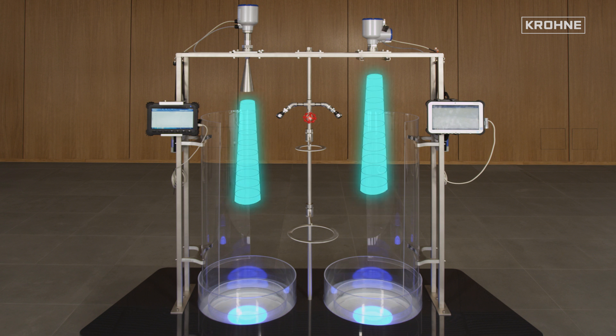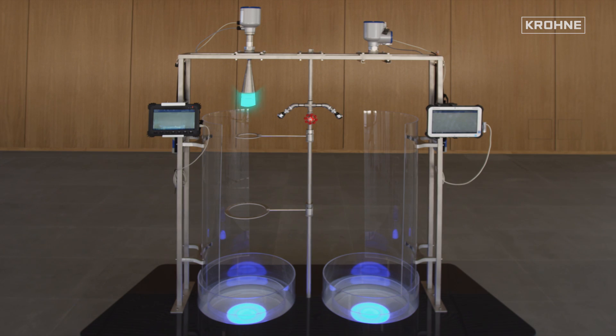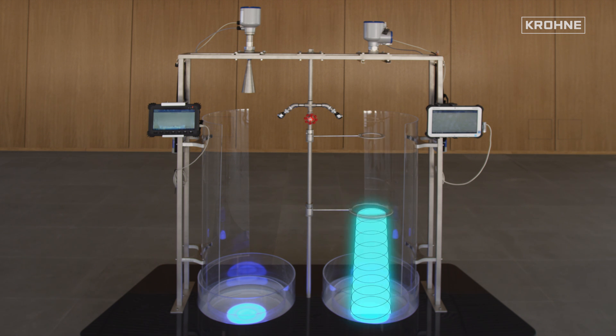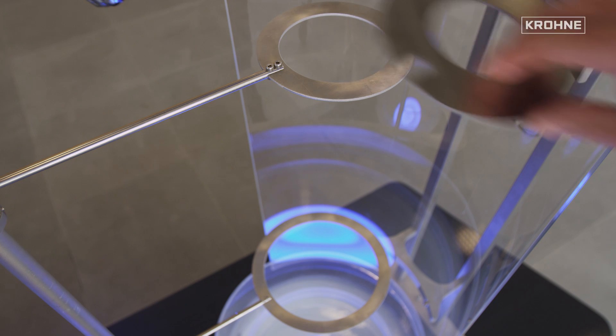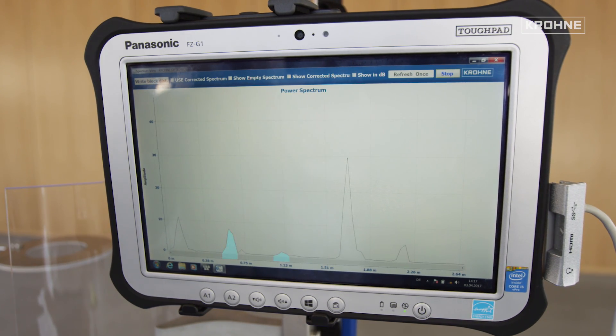In this comparison, the radar beam can be demonstrated by using metal rings. In both systems, the radar beam travels through the ring opening. As a result, the rings are hardly visible in the reception signal. If the ring opening is reduced, the radar beam hits the metal surface and the ring is clearly visible in the received radar signal.